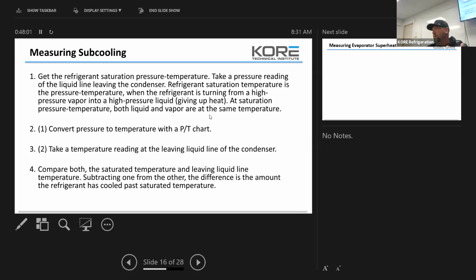So what you guys are going to do is look for that drain leg coming out of the condenser. The drain leg is where it's condensed to liquid, right? Because we're checking subcooling, we have to be checking a liquid, correct? So that's how you remind yourself. If I'm looking at subcooling, I want to look at how much I've cooled past the point of saturation, past the point that it turned to a liquid. Okay, so that's what I'm looking for.